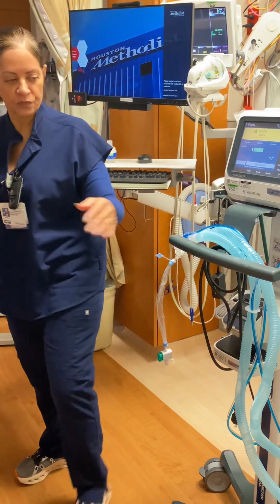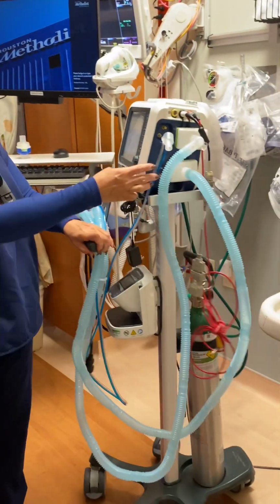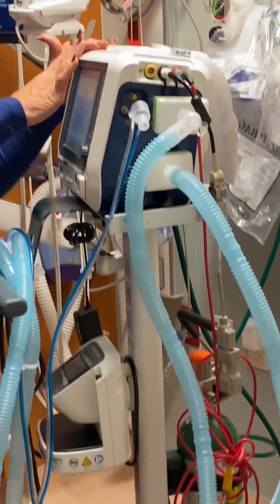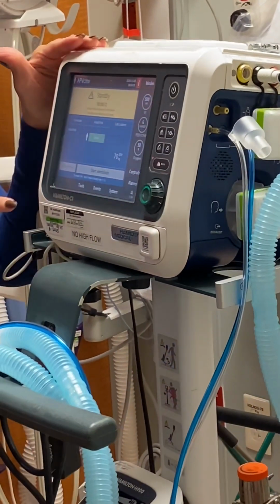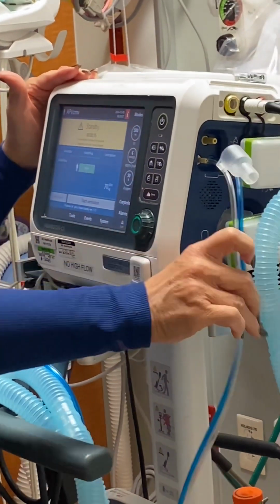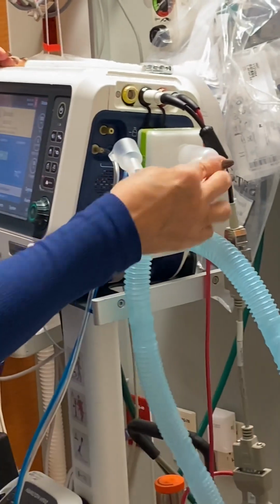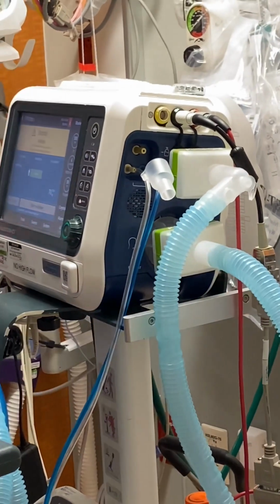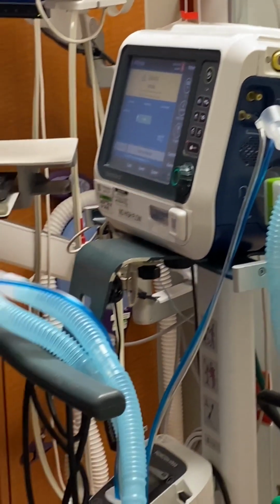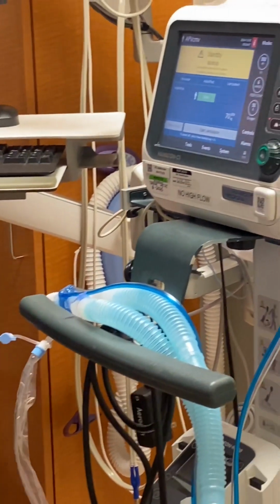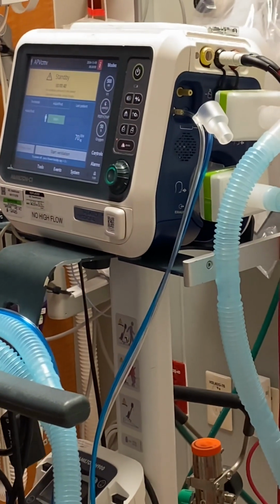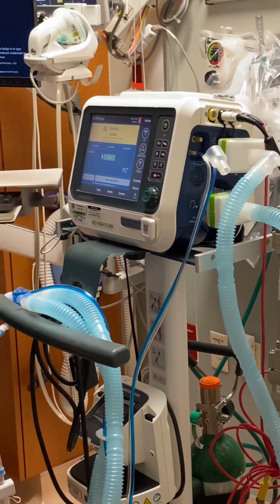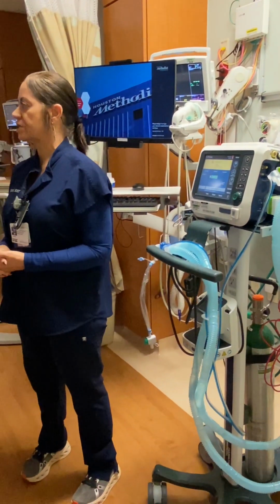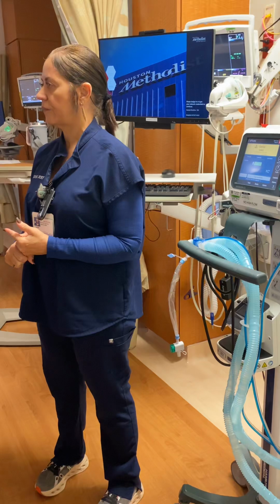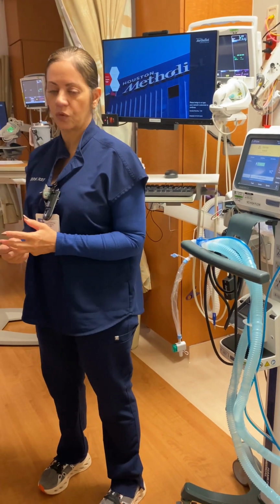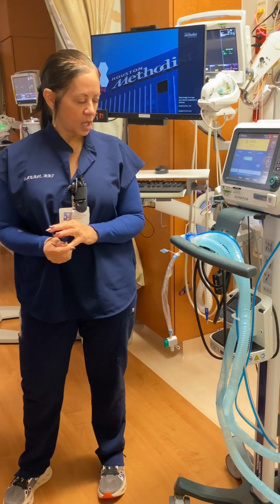Well, what can come loose? There's several pieces on here. This is called a flow sensor, which gives you all the readings, all your exhaled readings on the vent. This is where this fits, right here. This could be open. One of the tubing could have come apart, or this could be open. There's several things. Respiratory, you call the lead respiratory, or you call respiratory to come up and check it. I would always recommend call lead respiratory on the Vocera. That's the quickest way. Get us to come here and check on it real quick.